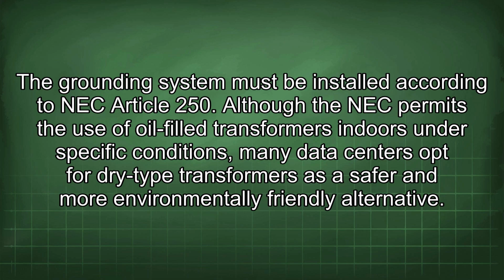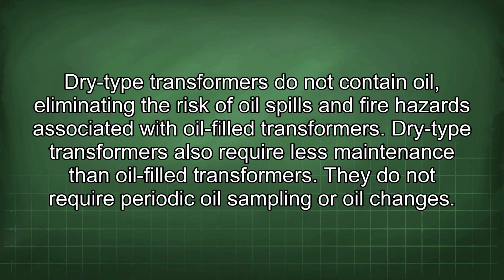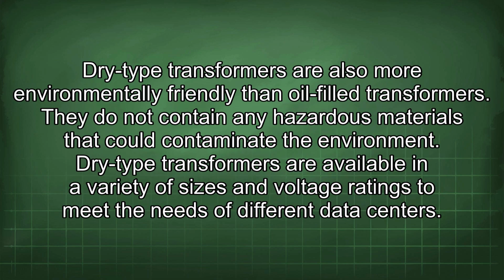Although the NEC permits the use of oil-filled transformers indoors under specific conditions, many data centers opt for dry-type transformers as a safer and more environmentally friendly alternative. Dry-type transformers do not contain oil, eliminating the risk of oil spills and fire hazards associated with oil-filled transformers. Dry-type transformers also require less maintenance than oil-filled transformers. They do not require periodic oil sampling or oil changes. Dry-type transformers are also more environmentally friendly than oil-filled transformers. They do not contain any hazardous materials that could contaminate the environment.